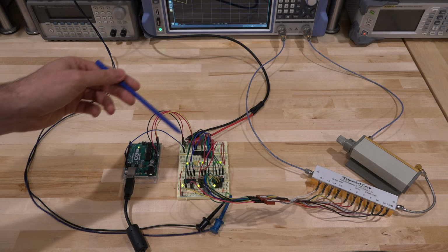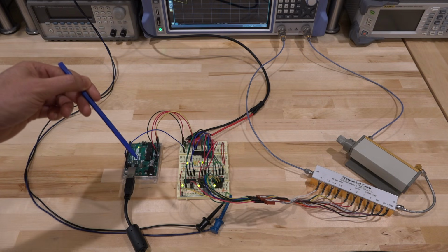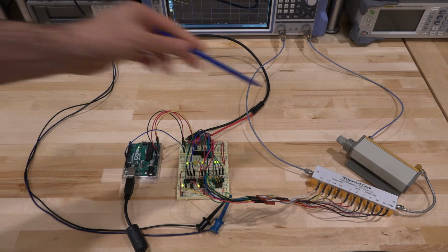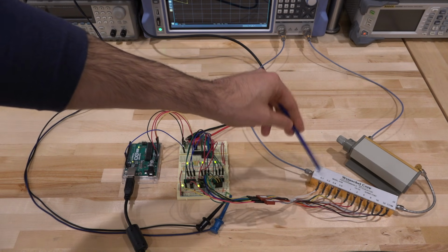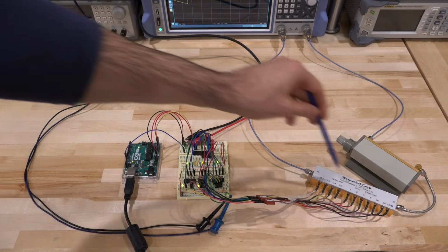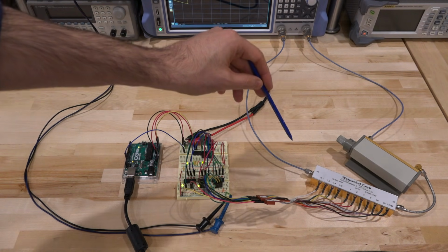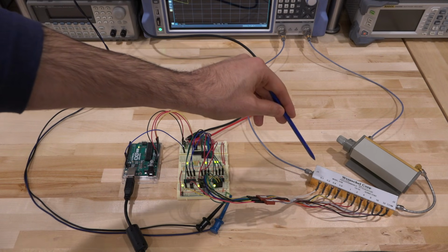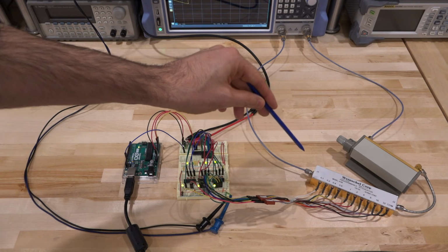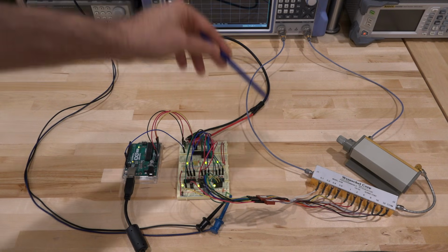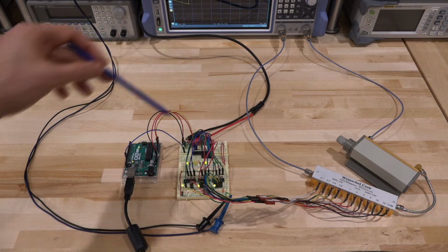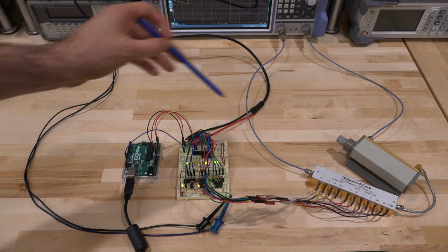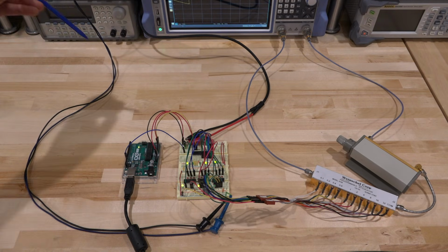The attenuator actually has only 10 bits, and that means it has 1023 states. And if you look at the attenuator over here, this is a very good model itself, and 10-bit attenuation, electronically controllable, that's really good. And because it's mechanical, its repeatability is excellent, its linearity is extremely high, and for the powers we are using, it's not going to suffer any thermal drift or anything like that. And so we're going to use that to basically test the network analyzer.